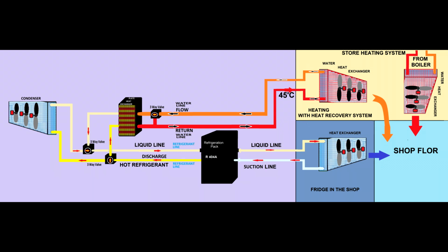If you use a heat recovery system without a boiler incorporated, then you have a different source of heat in your store. Before you check the heat recovery system, please just check your heating system, because if there is no heating system in a store, there might be nothing to recover. Remember, with a heat recovery system, the word is recovering: you're not creating heat, you just recover the heat that is removed from the store by the fridges.